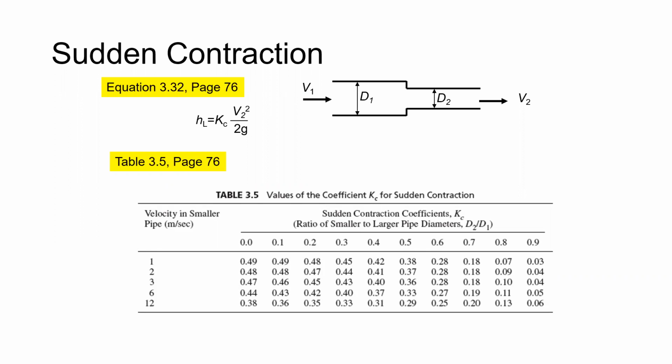Yeah, you lose more at the sudden. You kind of think of rough angles as causing more friction or more turbulence. That is why if you look at our HVAC system, you see gradual contractions, because this is a pipe flow problem. Different density fluid, but we want to make sure we can maintain pressure all the way to that very last register so that we get the flow rate we want out of that. So HVAC is very much consumed with losses in pipes and making gradual transitions as we go from one size pipe to the next. Because again, if you just had a right angle and a really sudden contraction, then you're going to lose pressure and you're going to lose energy, and so you're going to have less pressure at the end of the system to deliver that air.